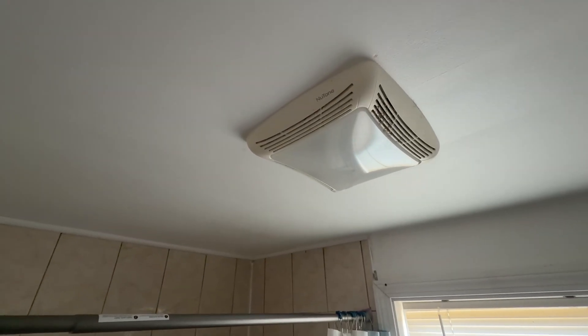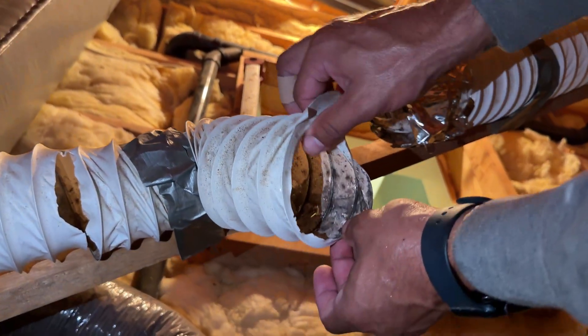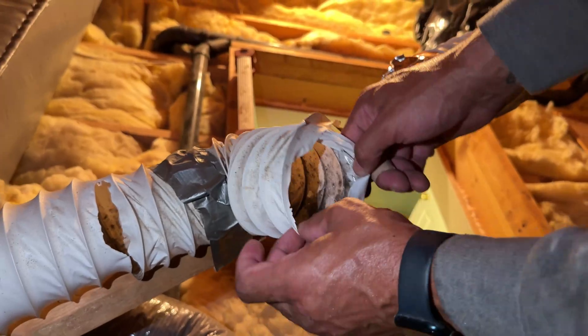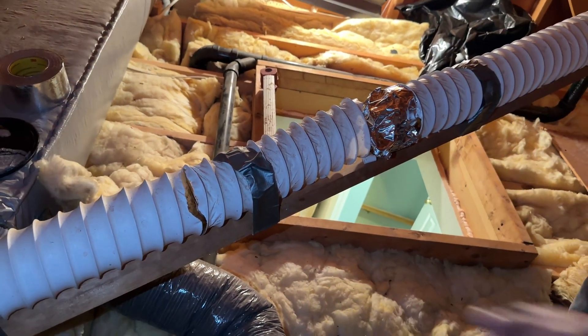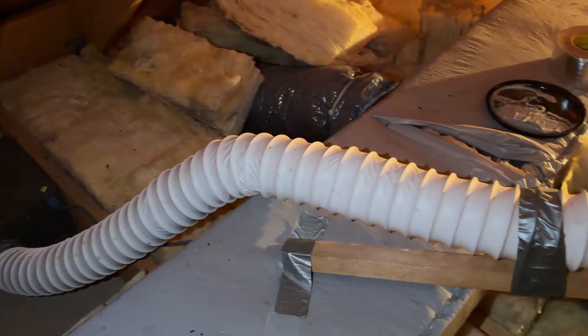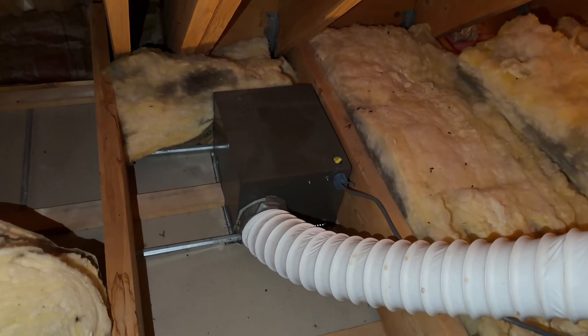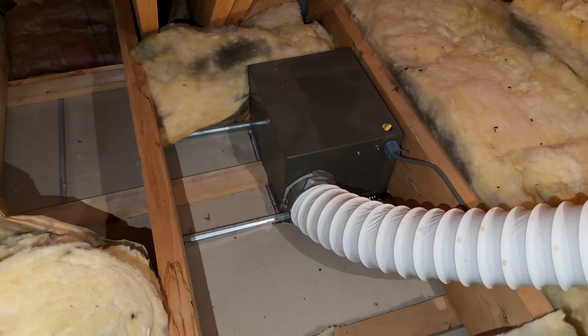There's a bathroom underneath and a fan coming up from there. The old vent here was not properly venting, so condensation was building up — hot and cold air colliding depending on the season — which started building what they call MLS, a mold-like substance, which over time could end up on your roof decking. Adding an insulated hose here and sealing the bath fan, properly vented out, will stop that. The insulated hose keeps the surface warm so humid air makes it all the way out without condensing. They also put a loop at the end so any moisture travelling back can't make it back into the bathroom.